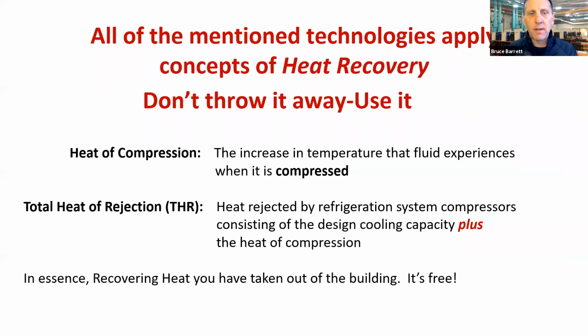So just quick definitions. When we're making hot water with a chiller, basically we're using the heat of compression. When that compressor operates, when it compresses that fluid, it creates heat. We're able to calculate that heat rejection plus some energy that we've extracted from the chilled water side. So we're adding the heat of compression to the extracted heat, getting our total heat of rejection.